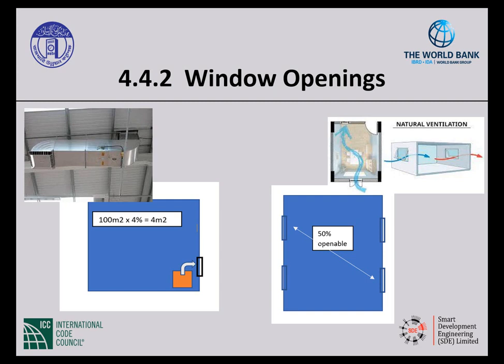Now let's talk about window openings. It's a little bit confusing when you read it the first time, so I just want to walk you through how to use it. So 4.4.2 tells us about mechanically ventilated and cooled buildings, so you have two different kinds of ventilation. Mechanical ventilation, where you're forcing the air through mechanically, or natural ventilation, where you have openings in the building and it's coming through naturally. So this is telling us, firstly, that if you have a mechanically ventilated and cooled building of occupancies other than hazardous, retail and storage, they have to have provisions for using natural ventilation for cooling and fresh air in frequently occupied areas.